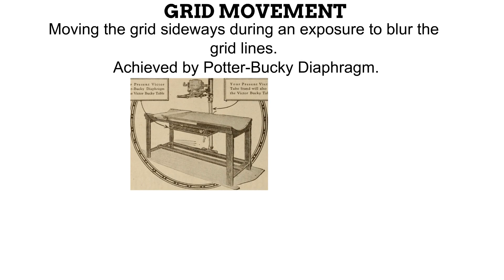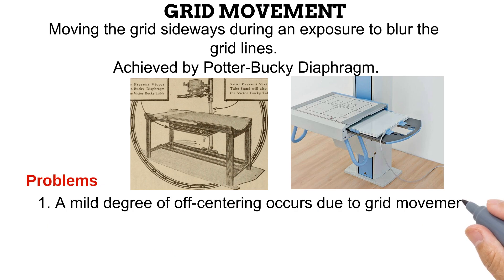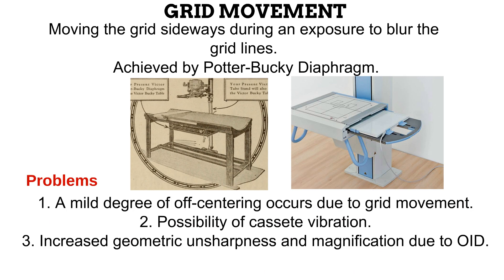The Potter-Bucky diaphragm was originally fitted under the X-ray table but has advanced into other forms, such as the erect Bucky used for erect radiographic exams. However, grid movement has a few setbacks. First, a small amount of off-center errors can occur due to the sideways movement. Also, the movement can cause the cassette to vibrate, leading to motion unsharpness on the image. Lastly, the Bucky device does not allow the cassette to be in contact with the anatomy, introducing object-image distance that causes some magnification and geometric unsharpness.